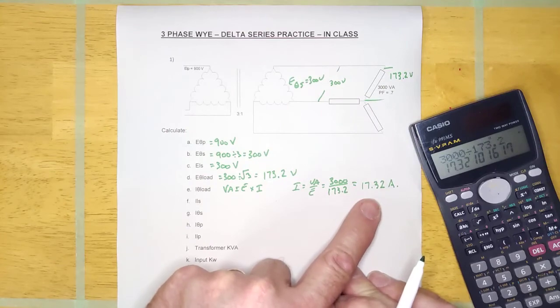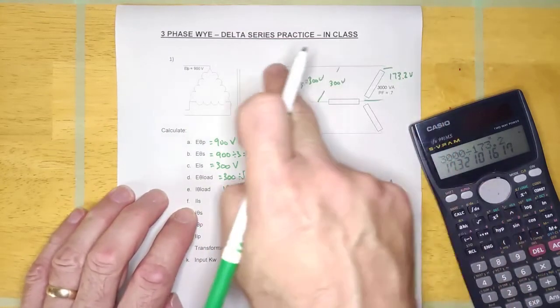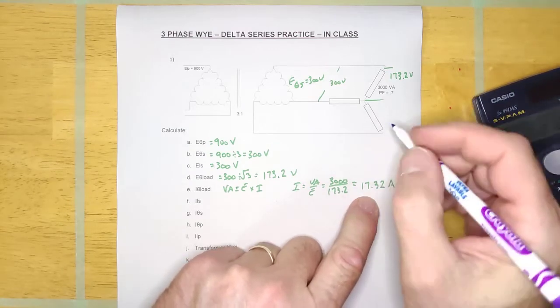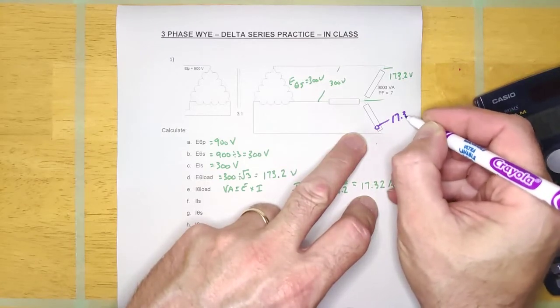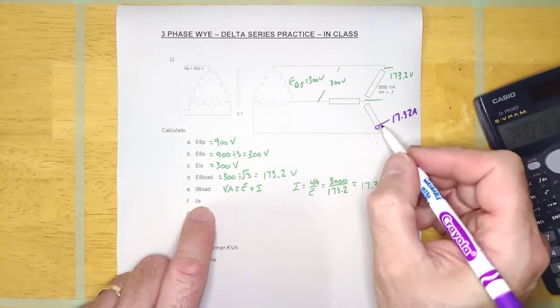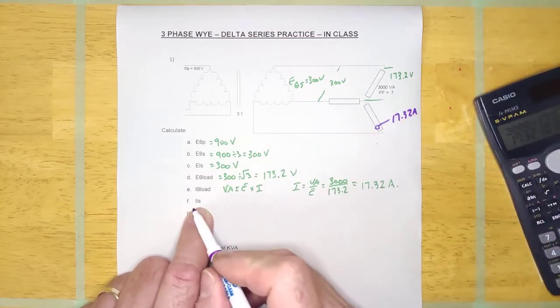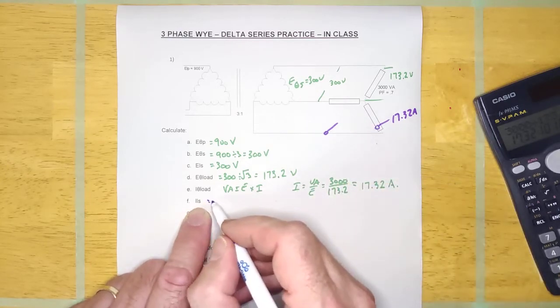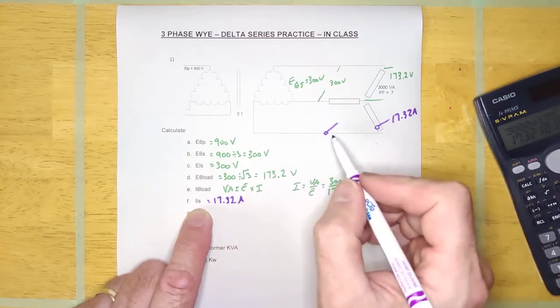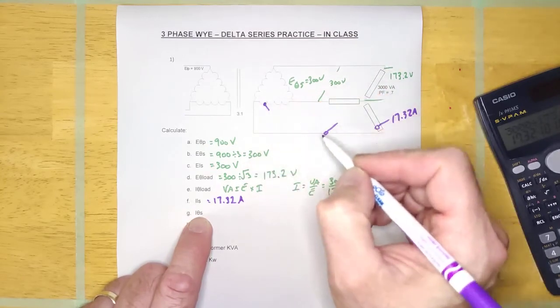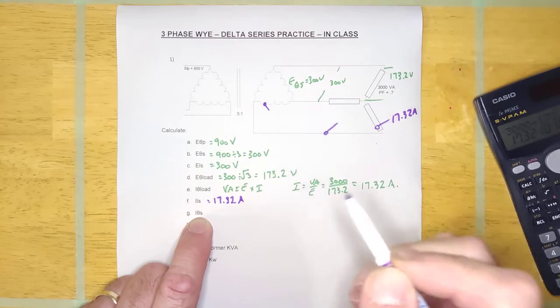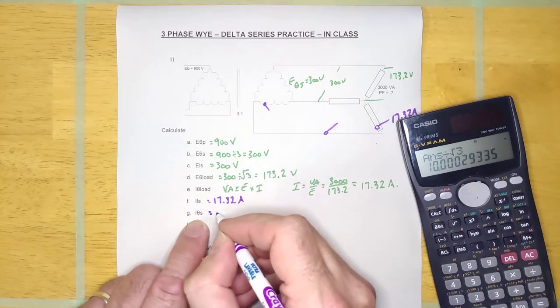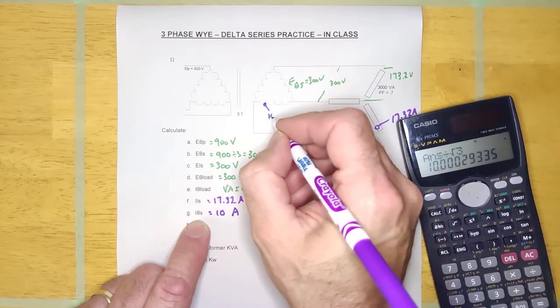Now it's just a matter of bringing that current back through the circuit. That 17.32 amps is I-phase load. Next is I-line secondary — even though it says line secondary, we look at the Y load: I-line secondary is right there and it's going to be all 17.32 amps. Then I-phase secondary: that 17.32 amps splits at the delta, so I-phase secondary equals 17.32 divided by root 3, which is 10 amps.